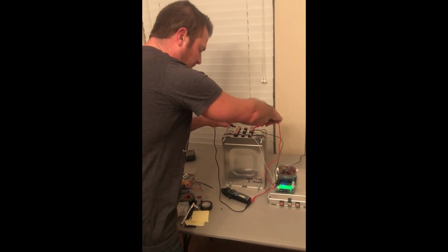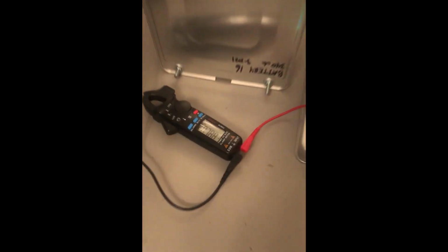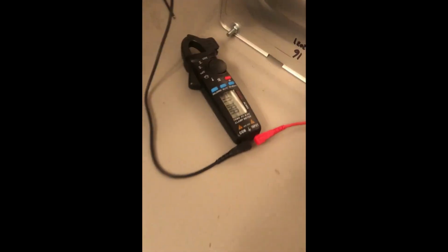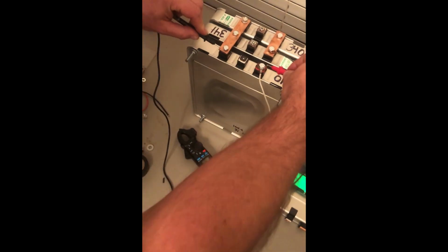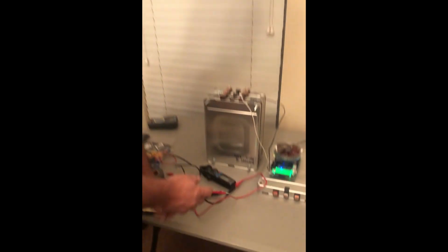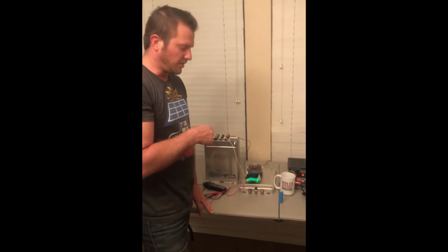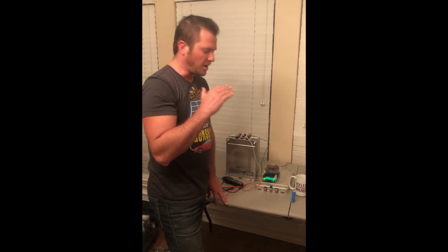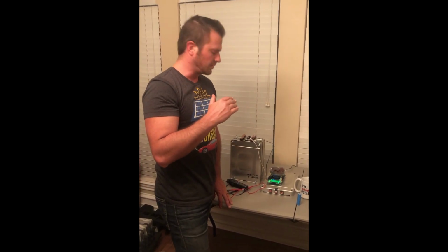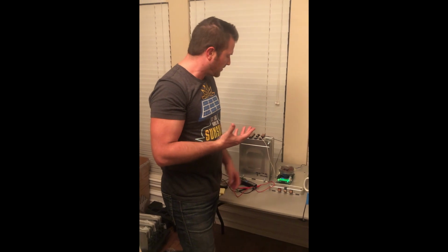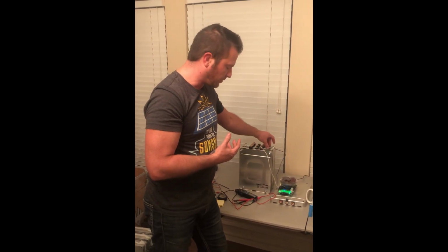On the back module we've got 7.88 volts, and the middle one also stays at 7.88. But when we jump to the second group and test that, it's all the way down at 6.36 volts—actually a little below the healthy discharge threshold of these modules, which is around 6.4 volts. So why did so much more power come out of this one than the other two?